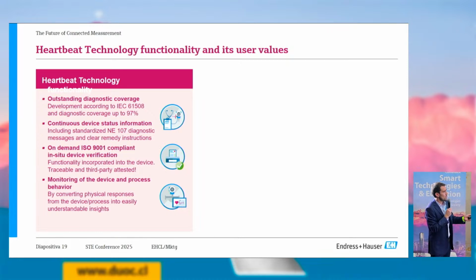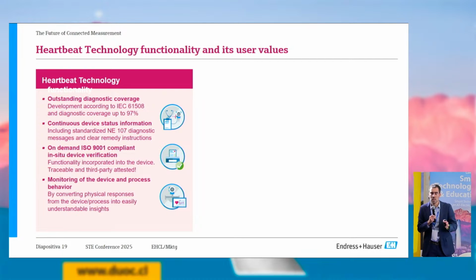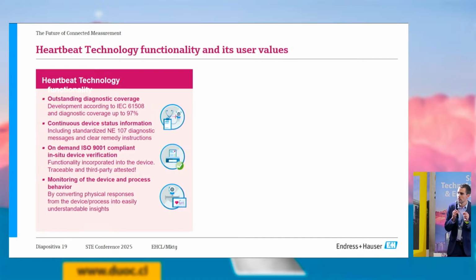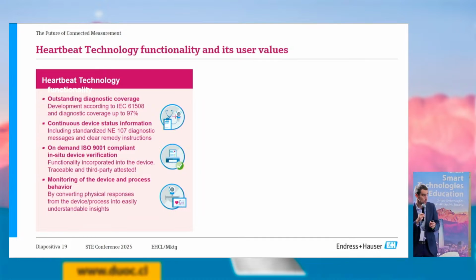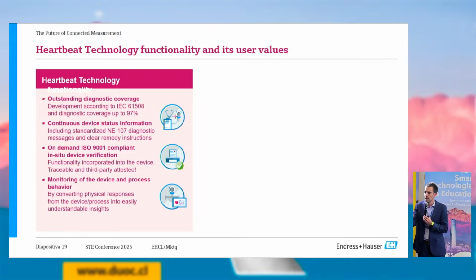As I mentioned, outstanding diagnostic coverage up to 97%, where that remaining 3% is mostly related to calibration. So it is a lot. We're always challenged by people in the industry saying 'but I need to calibrate this device,' and we always respond: what about the status of that device? Why don't you start with a verification before? How will you compare this with something better if you don't know what is happening inside the measurement loop?